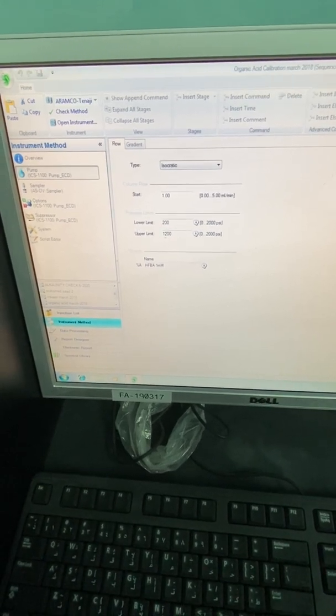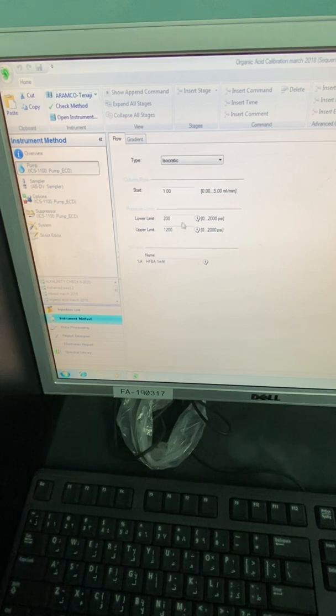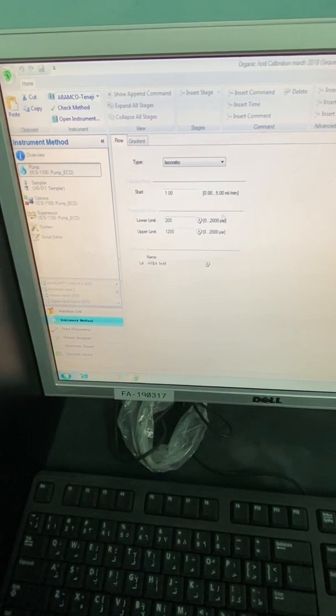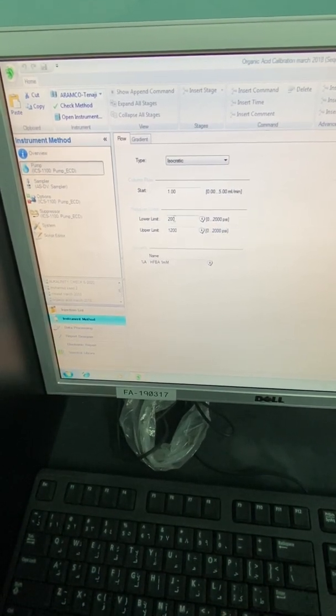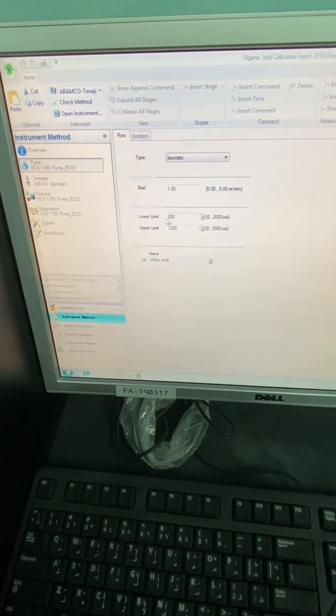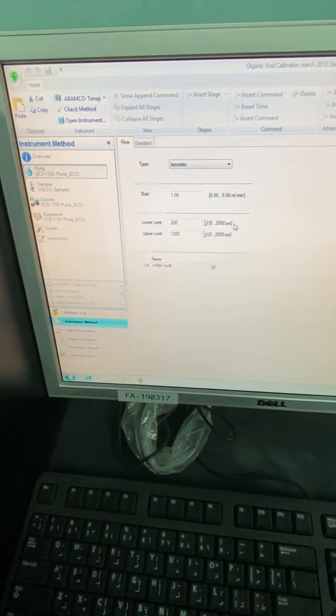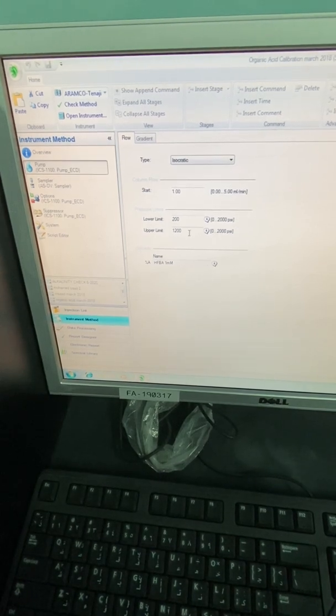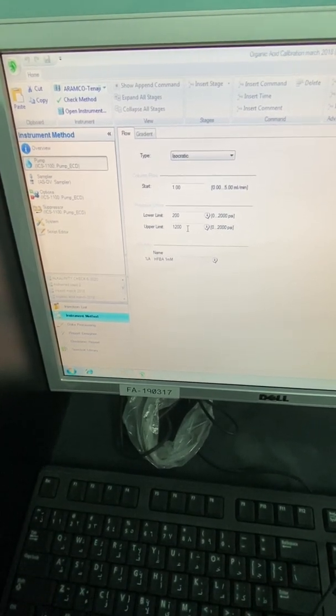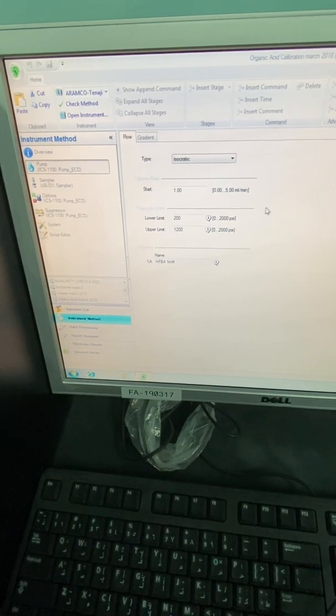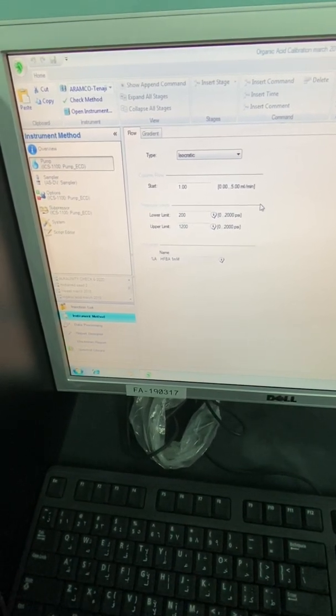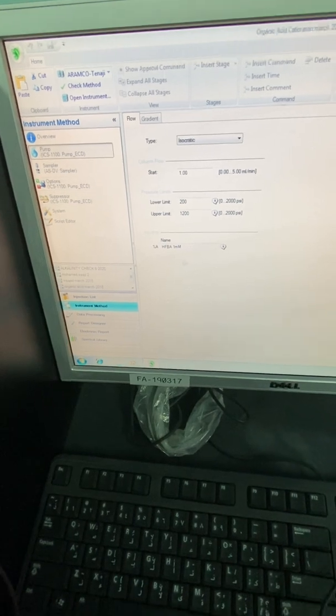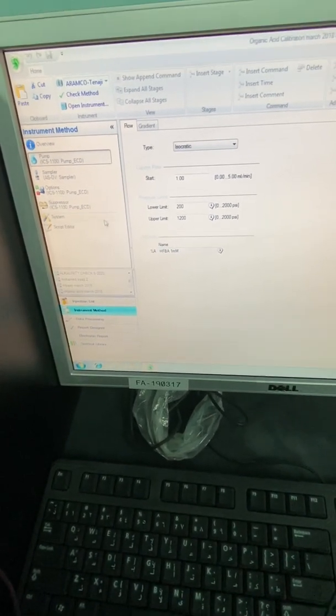This is like warning. You are putting lower limit and upper limit. In case there is no flow going from the column, that means the pressure of the system will be lower than 200. So for safety, it will be shutting down and give you alert. And again, for the upper limit exceeding 1200, this will give you alert. For some other applications, sometimes the pressure goes to 1400. This is the name of your solvent you are using.